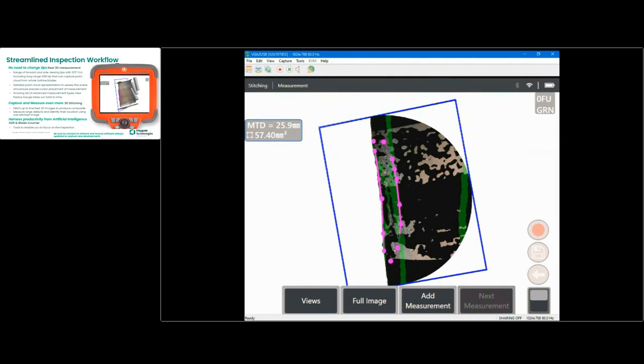I've just clicked on measurement image and been able to interrogate an area measurement that spans those three images. So this is a very powerful tool to carry out one measurement on one image once it's stitched together, rather than having to perform this on three separate images and then combine them together and compound the error associated with combining that. You can treat this like the other 3D phase measurement instances, an area example, using 3D stitching.